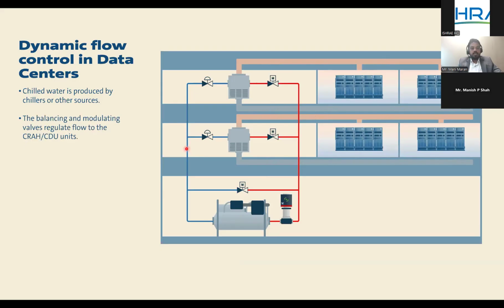So as I said, the balancing and modulating valve plays a major role in balancing the flow to each unit and modulating the flow based on the change in load of each unit. The modulating valve is regulated based on the feedback from the temperature sensor, and that creates the flow difference across the load based on the feedback from the temperature sensor.